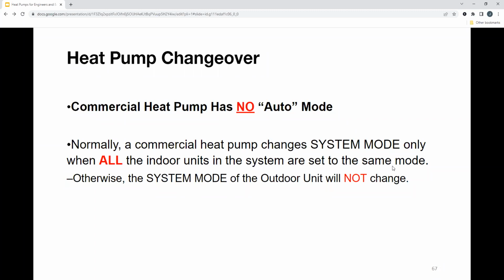So with that being said, if we are looking into a commercial heat pump that does not have simultaneous heating or cooling, it has no auto mode. So if you set it to auto mode, it's pretty much going to error out. You need to select either cooling or heating mode. And if you left it how it is, the bare bones changeover way is, let's say I have a condensing unit with 4 fan coils on the project, right? What's going to happen is all 4 of those fan coil units are going to have to be in one mode. Let's say they're in heating mode and 1 fan coil needs cooling mode. All of those fan coils need to turn to cooling mode before that zone gets cooling.